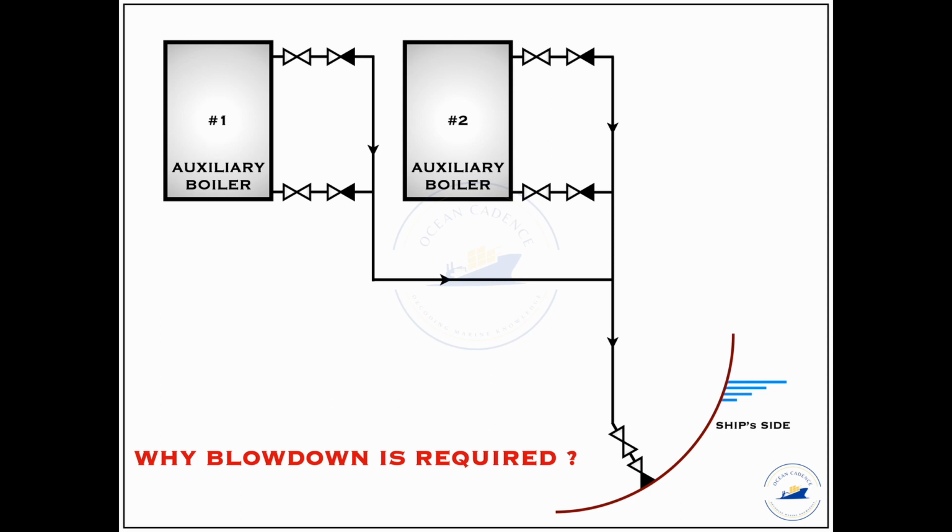So in order to counter these salts that are being generated and deposited in the system, we have to tend towards a procedure where we clear out the water that is now in a saturated condition, that is it has a certain amount of salts which is unnecessary, and top up the boiler with another freshwater dosage and add chemicals accordingly so as to maintain the ideal condition of the boiler water. This is where the boiler blowdown comes in place.